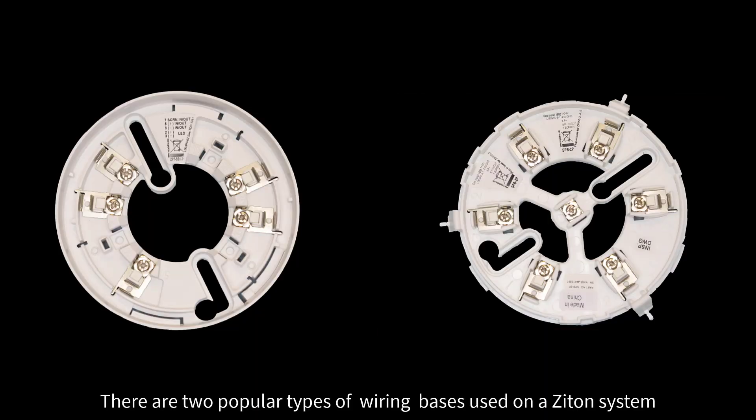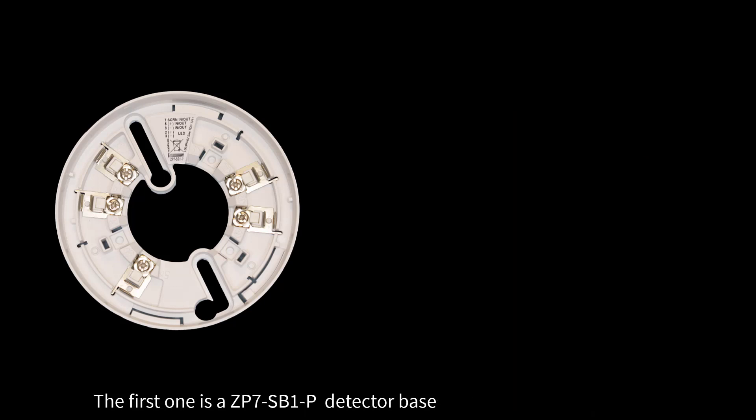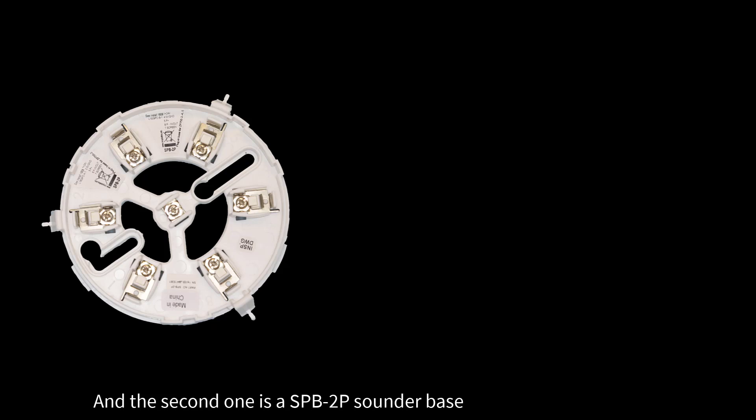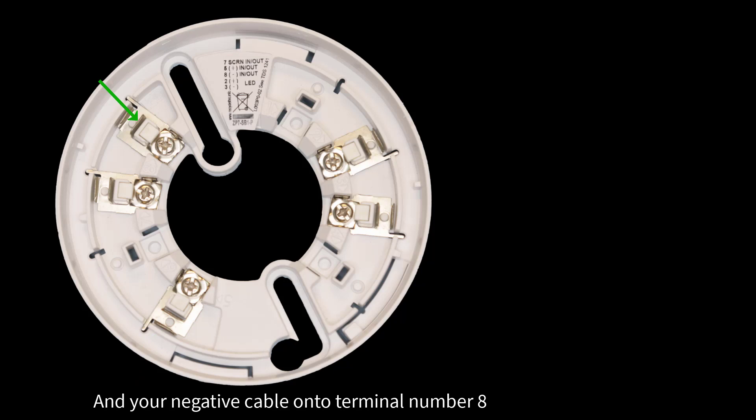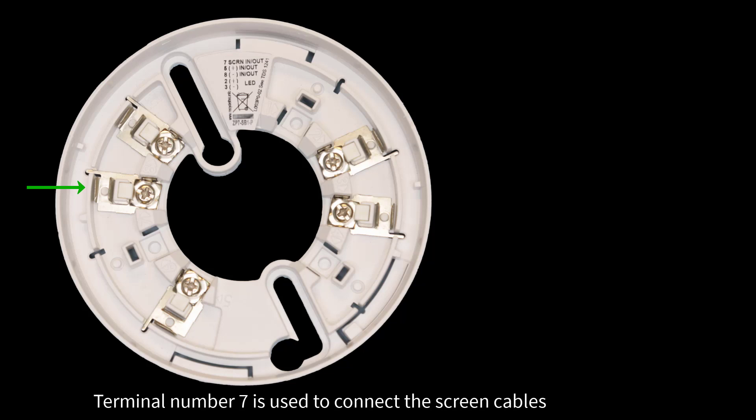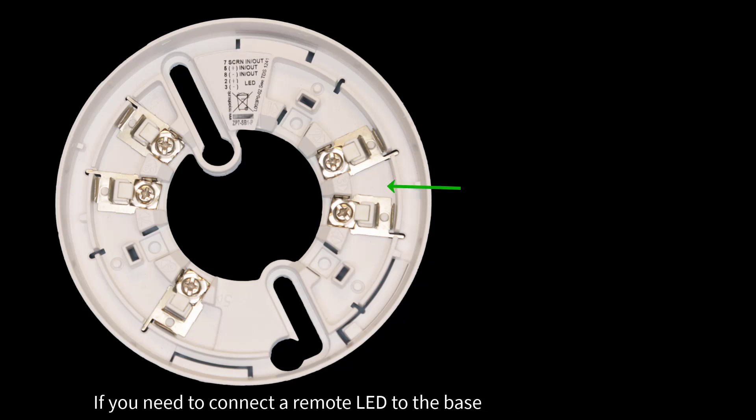There are two popular types of wiring bases used on a ZITON system. The first one is the ZP7-SB1-P detector base, and the second one is the SPB-2P sounder base. To wire a detector base, simply connect your positive cable onto terminal number 5 and your negative cable onto terminal number 8. Terminal number 7 is used to connect the screen cables. If you need to connect a remote LED to the base, simply use terminals number 2 and 3.